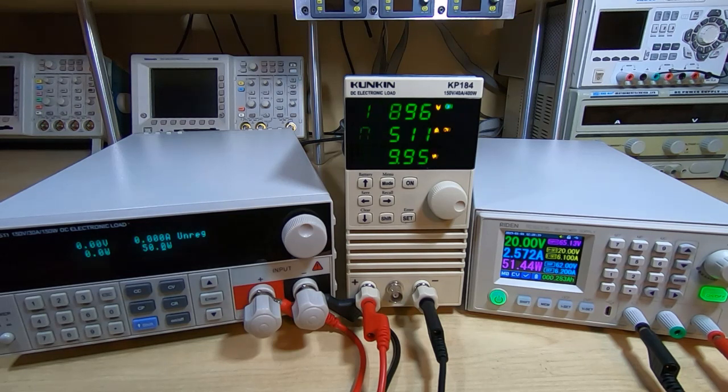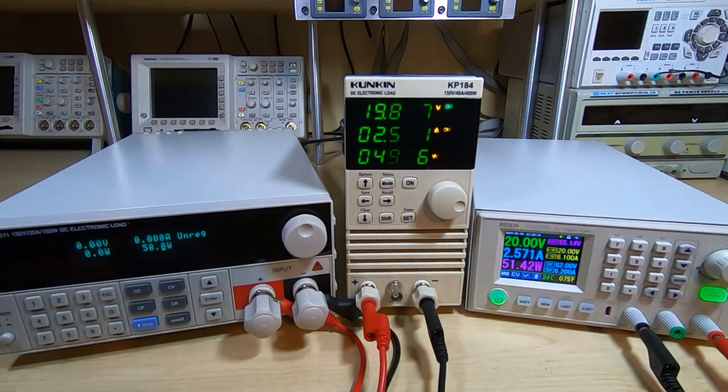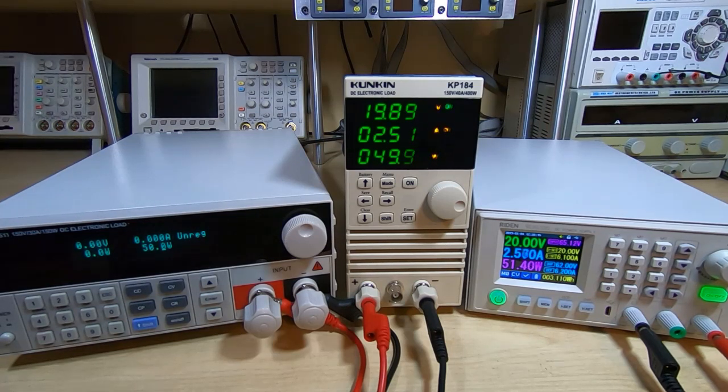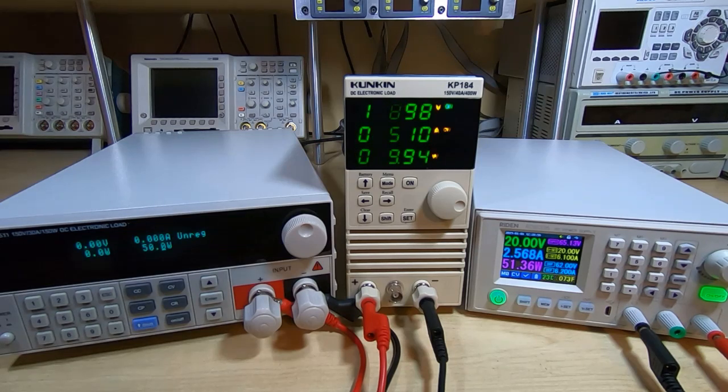It's not that unusual. Electronic loads quite often exhibit odd behavior. Bear in mind that if it's a programmable load, then it's an active device. It's got firmware it's running, it's trying to achieve certain targets. The behavior of this is, as I say, not unusual, but the instability could cause a problem because of the very high peak currents that were being encountered.